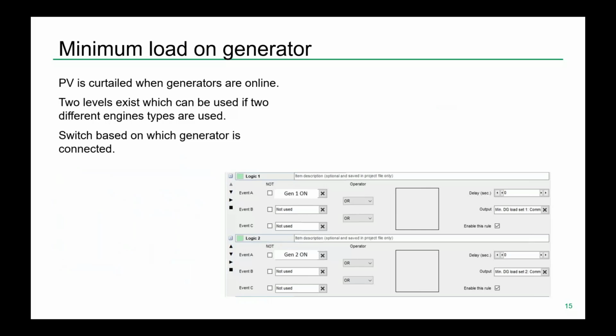Here you see a picture of our small programming tool. We call it mLogic. It is a small tool with 3 input conditions, and then you will drive an output. And here you can see I use one input condition. Generator 1 is connected. That will set minimum genset load set 1. Or if Gen 2 is connected, it will set minimum genset load set 2. So this way it's an easy swap between the two, and the controller does all the work.